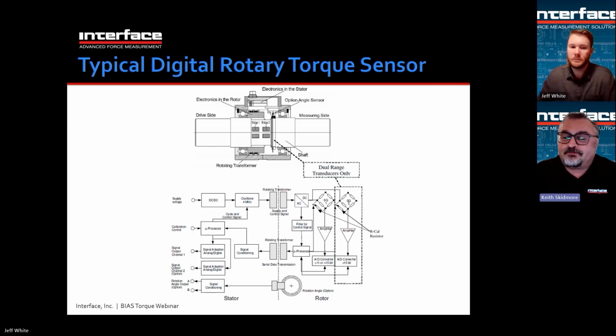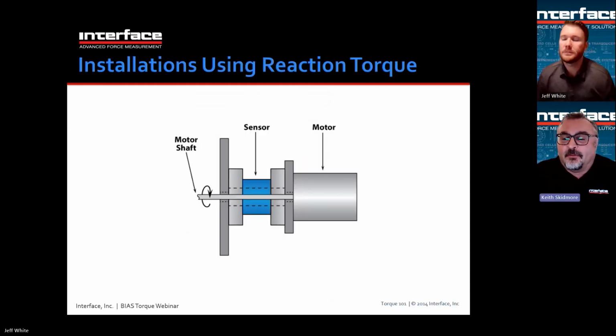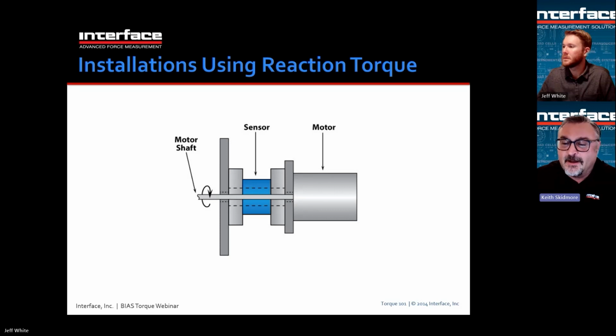Next slide, please. This is an example using a reaction torque sensor with a rotating shaft on a motor. People may ask, how does that work? If we have a rotating sensor, that makes sense, but how can we use a reaction sensor to measure rotary torque? Here's a very simple scheme where you have a hollow torque sensor. The blue sensor in the middle is hollow, with a hole going all the way through the middle. We have a motor mounted to one side of the torque transducer, and the other side of the torque transducer is mounted to a plate, and there's a hole in the plate. So the motor shaft spins through the torque sensor.